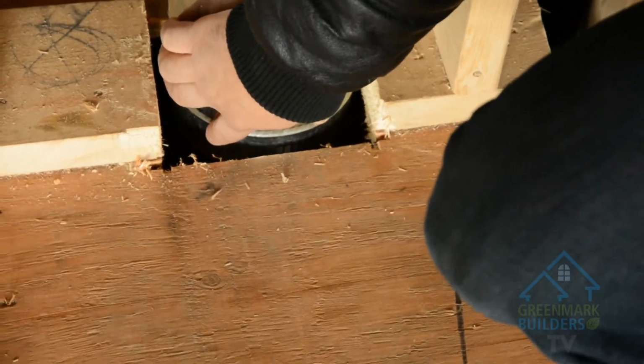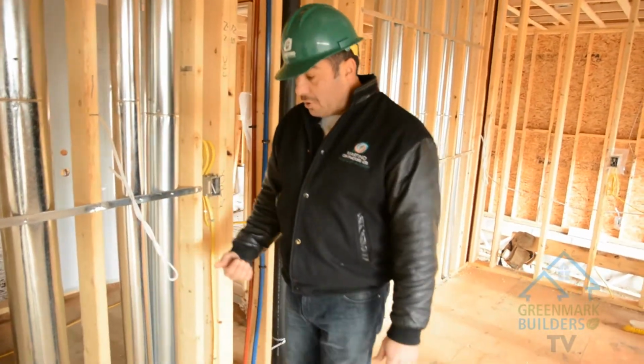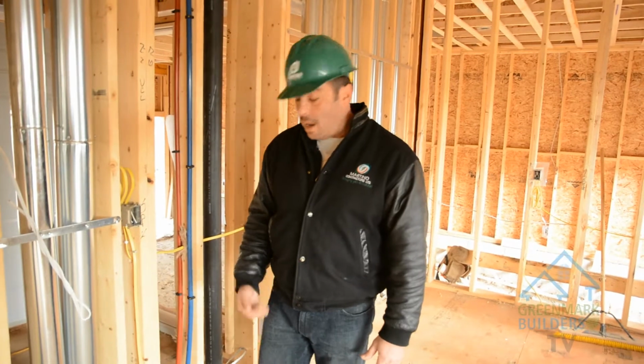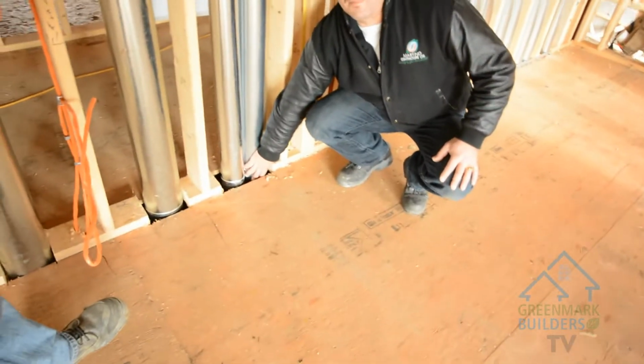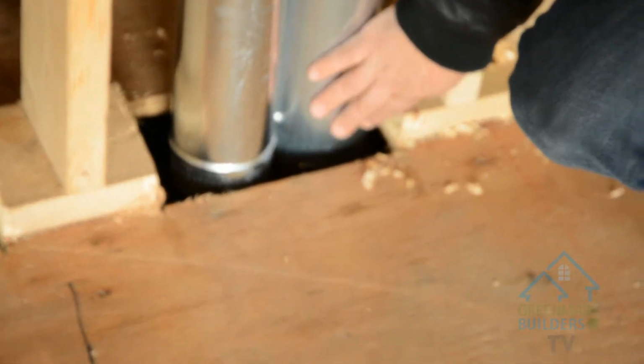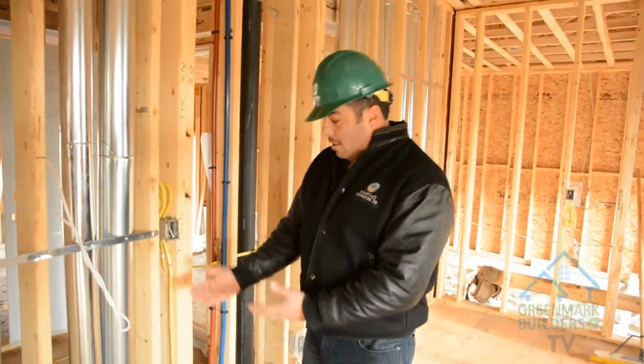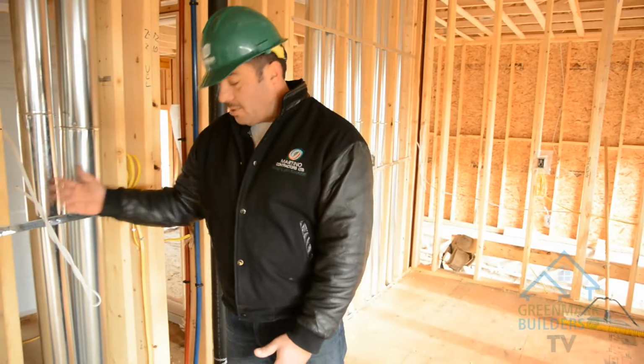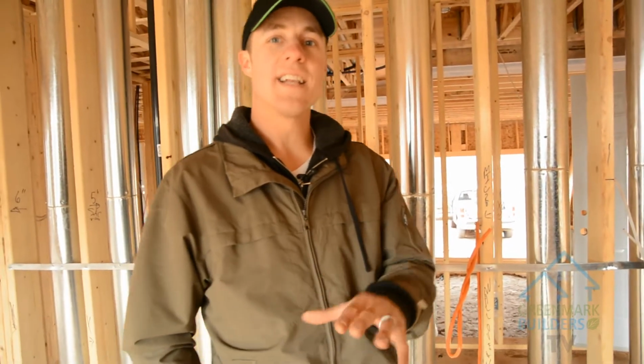I've got to trust my installers, and this is how we do it. You see the crimped end on this side? That's the return air, automatically, that's our standard practice. And for the supply air, when the guy's in the basement working on it, you see the smooth edge on the pipe here? That's the supply air. So the basement installer, reading the plan and looking at it, knows that's the supply and that's the return air, matching up with the plan. That's how we mark it, and by doing things like that you're limiting mistakes, and that's what it's all about.